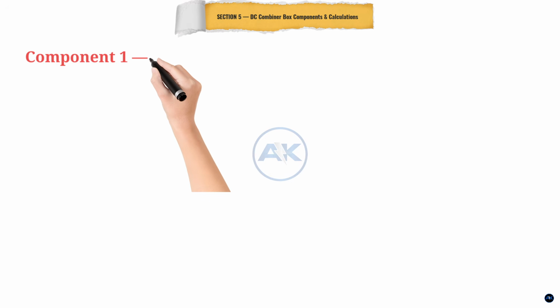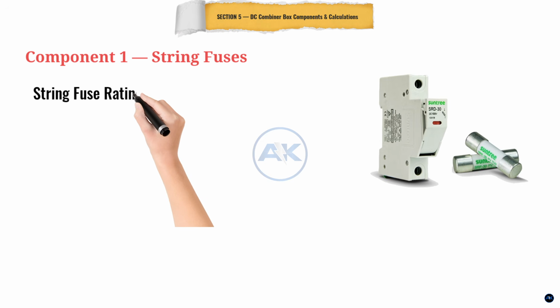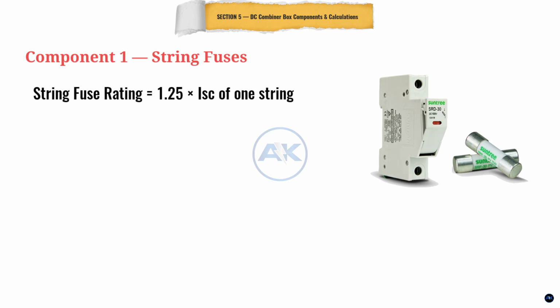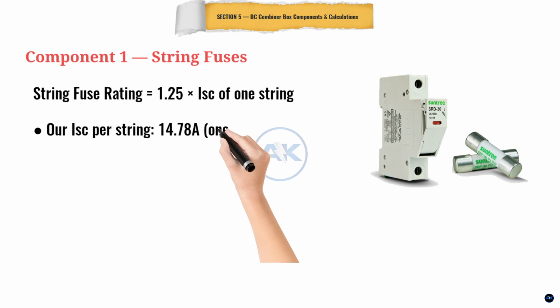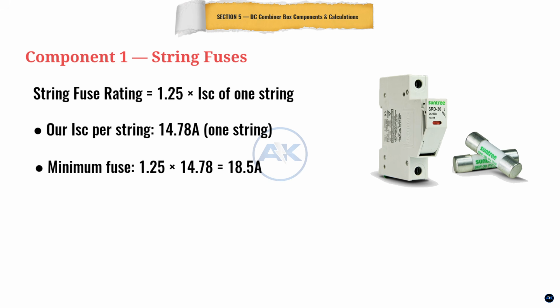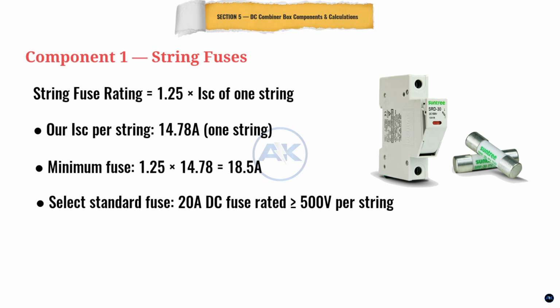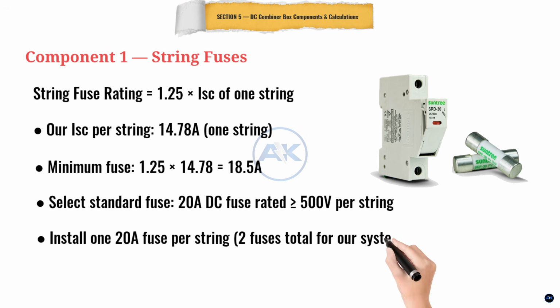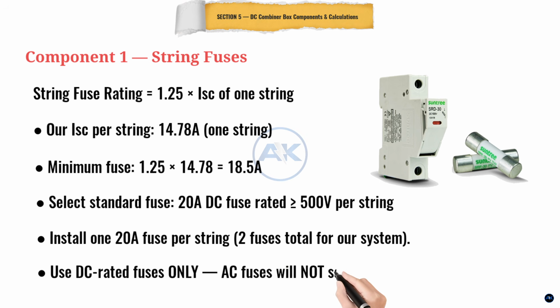First, string fuses. The rule is simple, 1.25 times the short circuit current of one string. Our ISC is 14.78 amps. Multiply by 1.25. That is 18.5 amps. We round up to the next standard size, 20 amp DC fuses, rated at 500 volts or higher. We need 1 fuse per string, so 2 fuses for our 2-string system, and always use DC-rated fuses. AC fuses cannot safely break DC current.